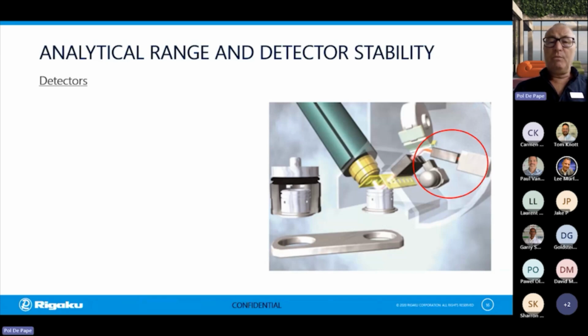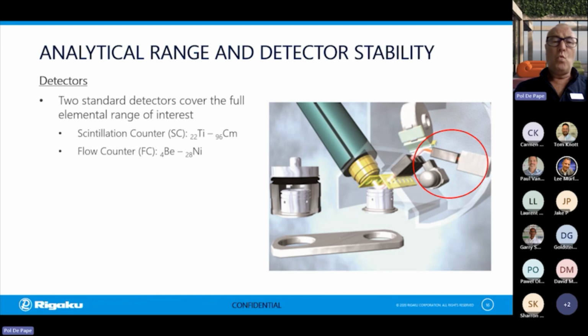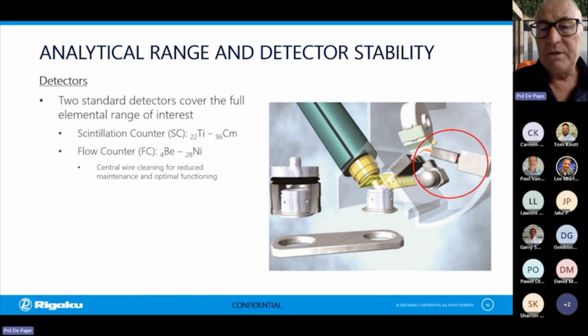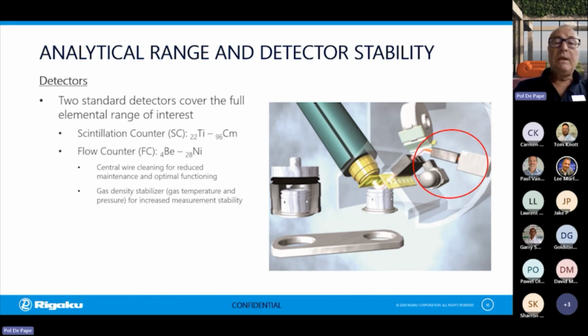After the crystals, we come to the detectors, 2 standard detectors, 1 scintillation detector, 1 flow counter to detect the full range of elements. What is important in the flow counter, we have a central wire cleaning, and the central wire cleaning we can activate through the software. So we do not need to open this detector to exchange the wire. And this is a very big advantage if you want to have a reduced downtime of the system. We also use a gas density stabilizer in this flow counter for increased measurement stability.